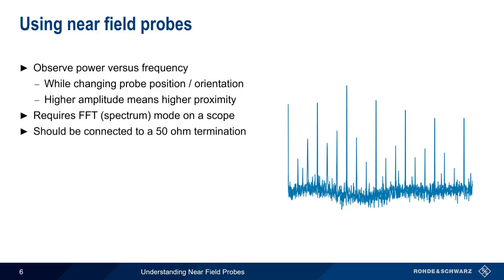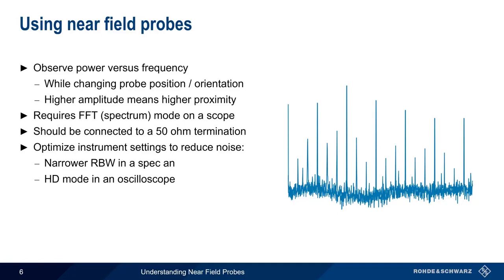Because the received signals may not be very strong, instrument settings should be optimized to reduce noise. For spectrum analyzers, a narrower resolution bandwidth is recommended, and using high-resolution or high-definition mode in an oscilloscope can also help to reduce noise. As we'll discuss in just a few moments, it's often a good idea to use different sizes and different types of near field probes.